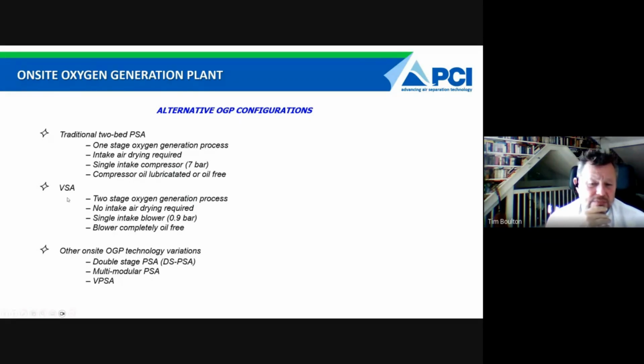The VSA system is 2-stage. There is no intake air drying required because the intake pressure is no more than 0.9 bar, so there is no condensation produced. The water vapor is caught in the molecular sieve and is blown out on the purging stage. The blower is completely oil-free.